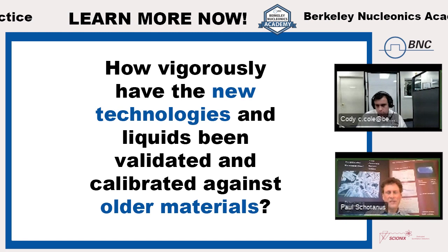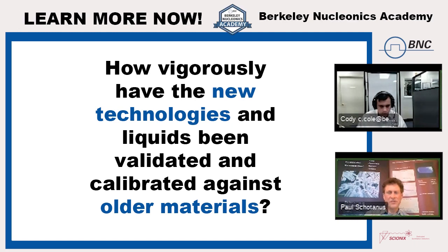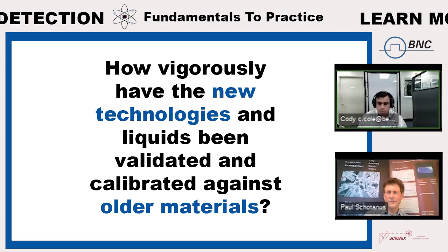The outcome is that there is a slight advantage in using the low flashpoint dangerous goods material, but it's really outweighed by the advantages of the much safer liquid, EJ-309. For most applications, 309 is perfectly adequate. There are several publications about it. We can look it up and send you the references. Excellent. Yes, definitely get in contact with us, Neil, if you would like those publications.